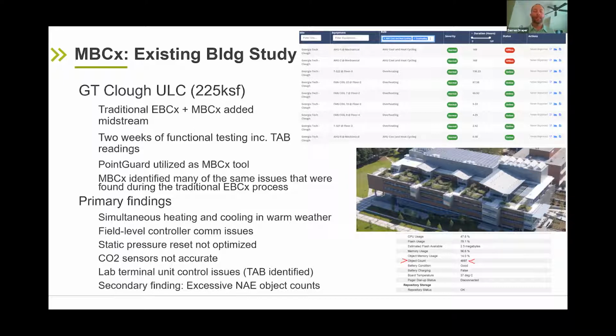So what are the primary findings we found with a combination of the two, with monitoring-based commissioning validating some of those findings? Simultaneous heating and cooling in warm weather, field level controller communication issues, static pressure reset not being optimized, a very common problem, CO2 sensors not being accurate, which is not probably surprising to many of you familiar with CO2 sensors since over time they do tend to drift, and they had some lab terminal unit control issues that TAB found, which largely require TAB measurements to find.